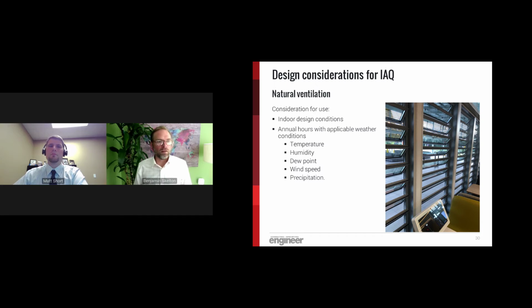When we look at a commercial-grade application where we're going to have an automation system control this, we want to make sure that the weather outside isn't going to make weather inside. And that can happen very quickly. Weather can change when a storm passes over, things of that nature. So generally, we will have a nice weather station on site that looks at things beyond what we normally look at in a lot of buildings: temperature and humidity, where we either measure the dew point or calculate it, and then wind speed and, of course, precipitation.